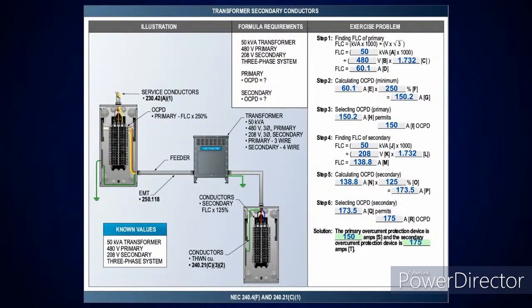Now, this one is where I'm going to do the primary and secondary. I've got a 50 kVA transformer, 3-phase, with 480 volts on the primary and 208 volts on the secondary. When I look at this table and pick up primary and secondary protection, I'm at a current of 9 amps or more, so I'm taking that 250%. And then when I look at the secondary, it says 125%. But isn't this interesting? The 125% has a superscript 1, but the one for the 250% doesn't. So I'm over that 100, which means I'm going to drop down on the 250%.